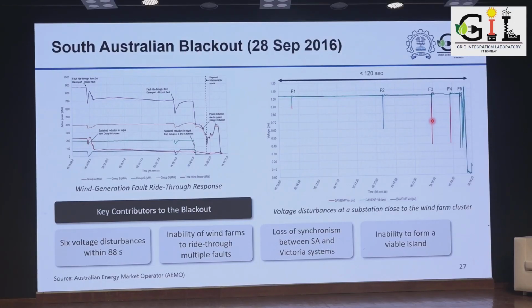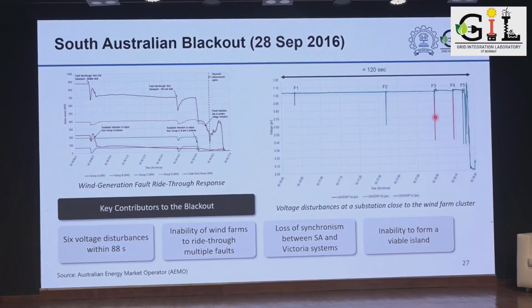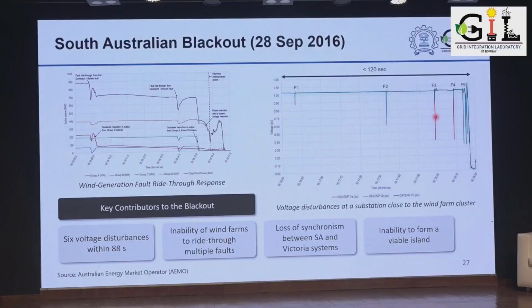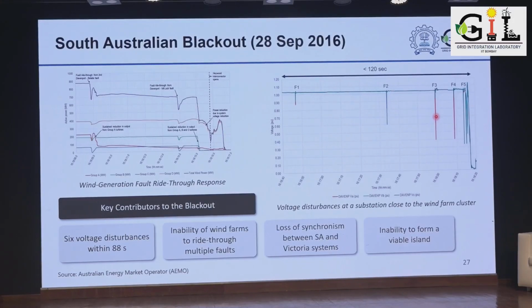The wind power plants reacted accordingly, and there's debate on how they could have and should not have responded. But there was no specific mention of recurring LVRT ride-throughs in the grid code regulation, and that was one of the major reasons for this event. So, after this event, they brought in requirements for recurring LVRT and HVRT voltage ride-through. These issues led to the blackout and highlighted unanticipated events and the responses of renewable energy plants.